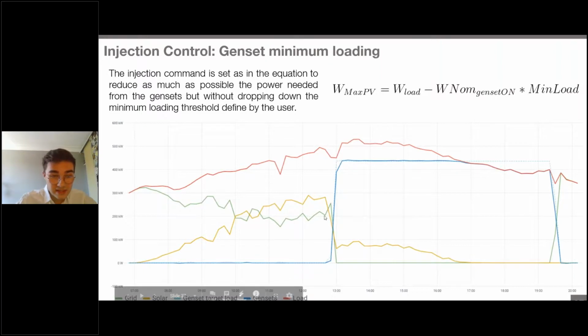In light blue you can see the genset target load, which was about 30% for this site. The genset power is equal to this target load as long as the load is higher than the minimal genset loading, and any additional power needed to correctly supply the demand is provided by the PV inverters.